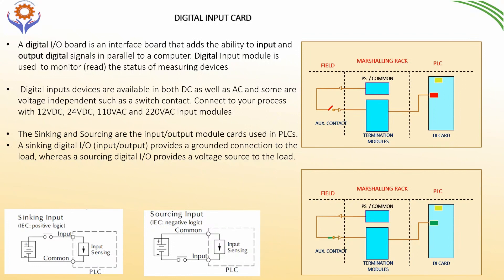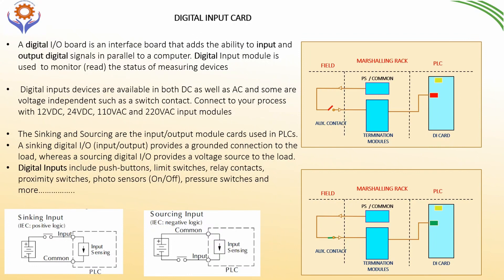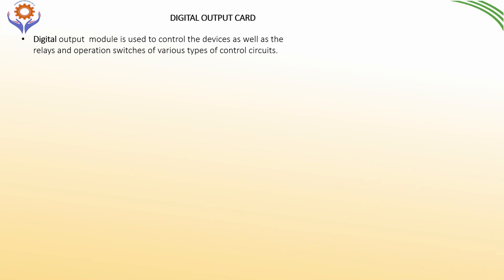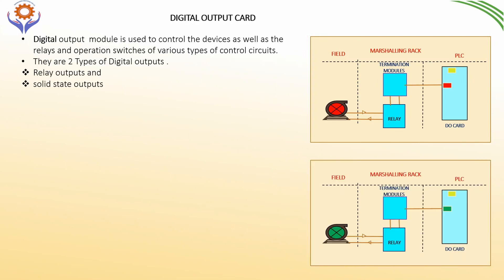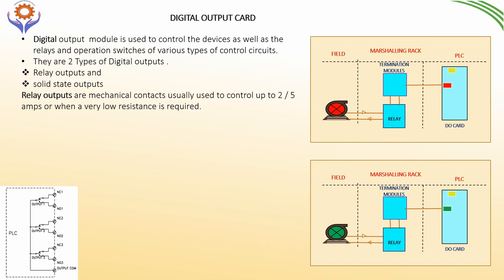Some examples of input devices include push buttons, limit switches, relay contacts, proximity switches, photo sensors, pressure switches, etc. The digital output module is used to control devices as well as relay and operation switches of various types of controlled circuits. There are two main types of digital outputs: relay outputs and solid state outputs. Relay outputs are mechanical contacts usually used to control up to 2 to 5 amperes or when a very low resistance is required.